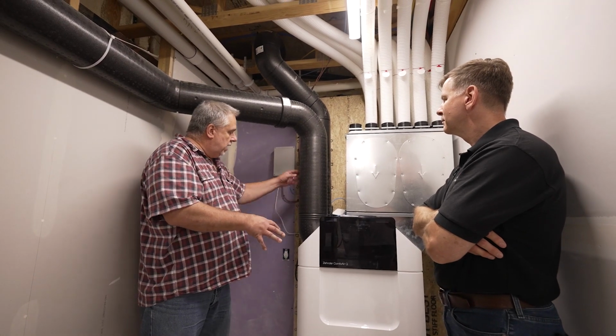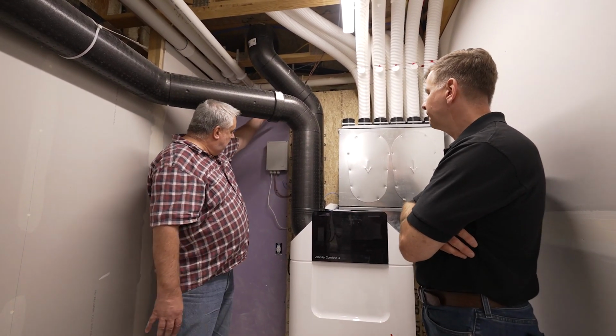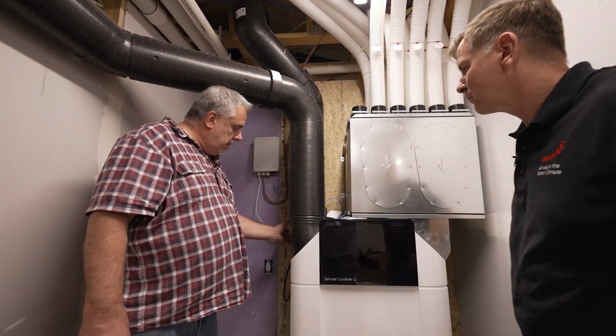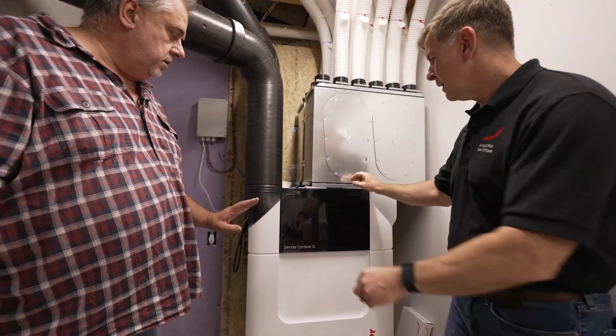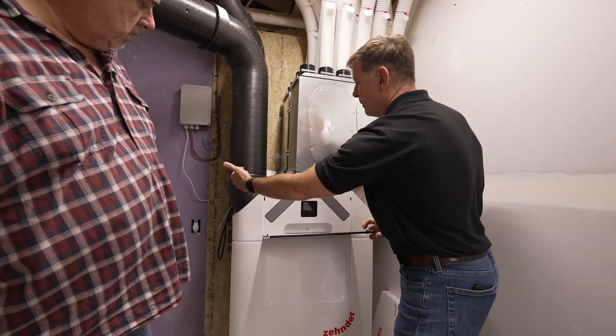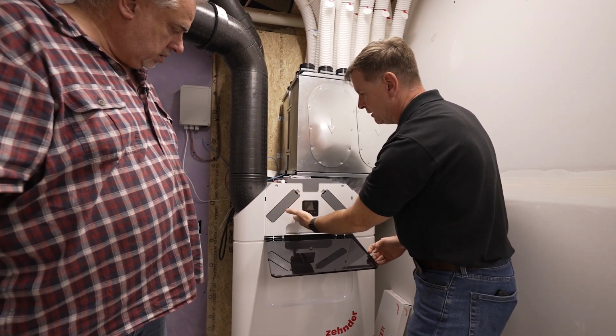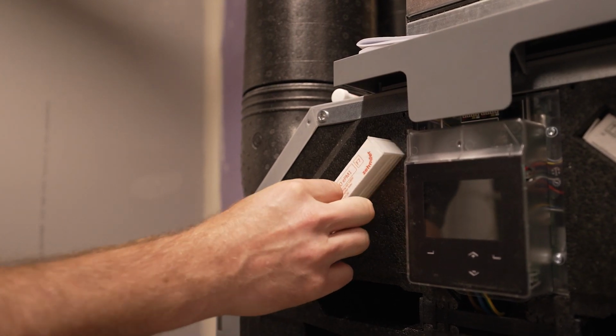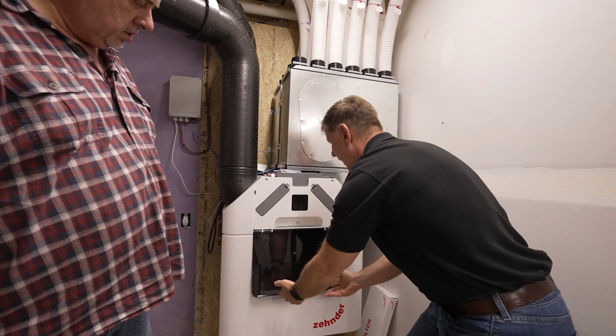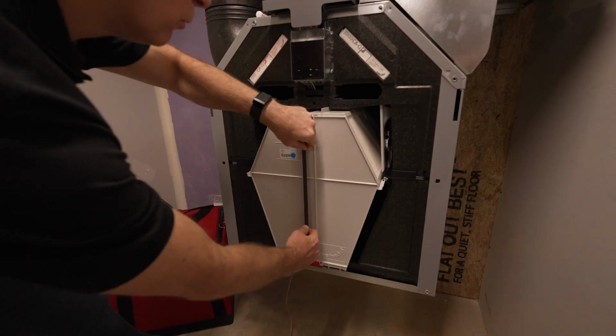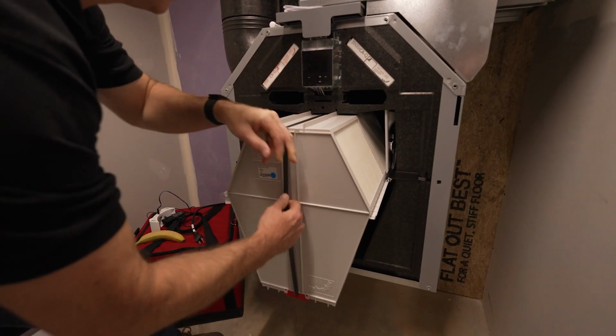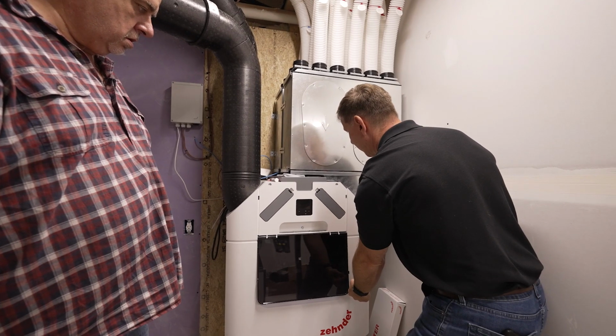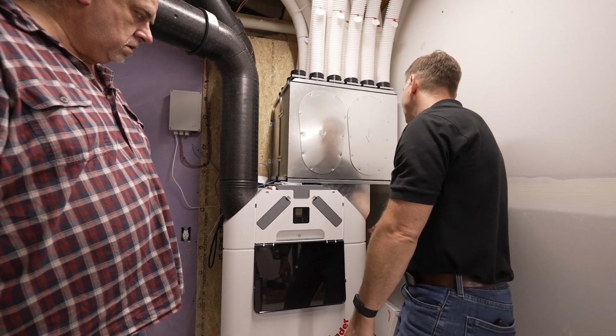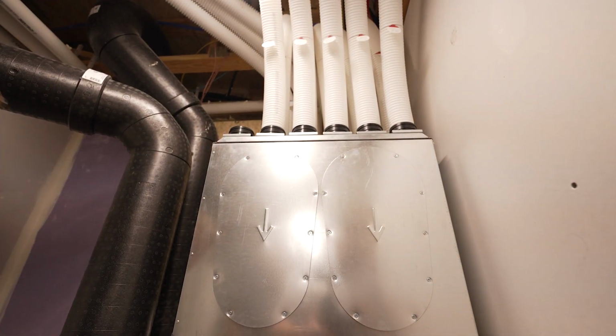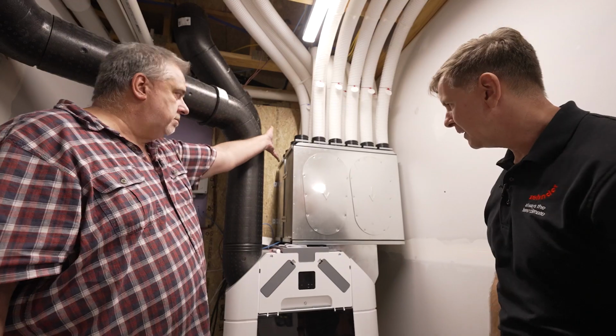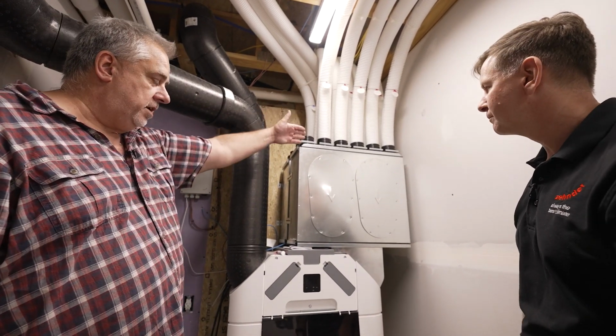We're bringing air in. So let's just trace that air for a minute, Chris. So the air comes in through this system, and it goes into this big white box. It's going to come in through that duct in the back. It's going to pass through a plenum that crosses this filter that's behind this cover. And basically, you've got your hexagonal heat exchanger core behind here. So the outdoor air is going to pass through the heat exchanger, get into this bottom plenum over here, and then it's going to feed through the box in the back. Right. So there's a twin of this box that's basically behind it. Yep. So there's 10 tubes there, 10 tubes here.